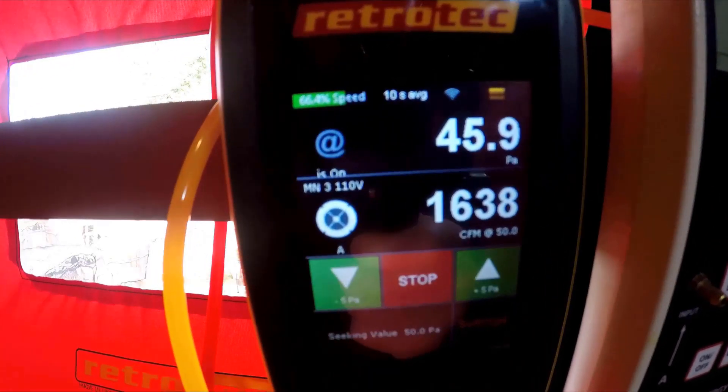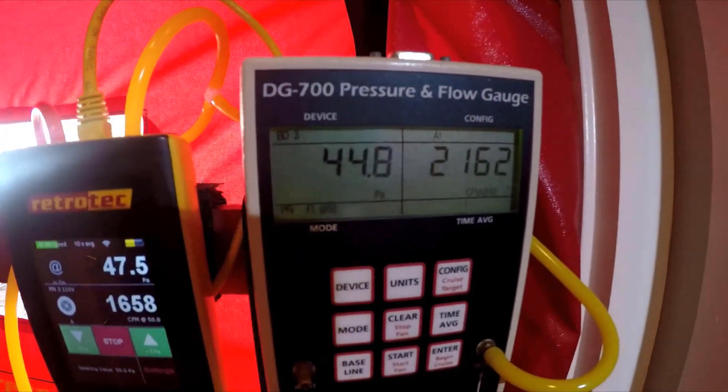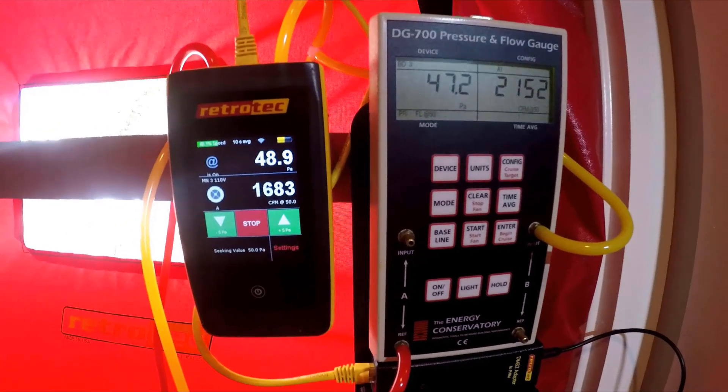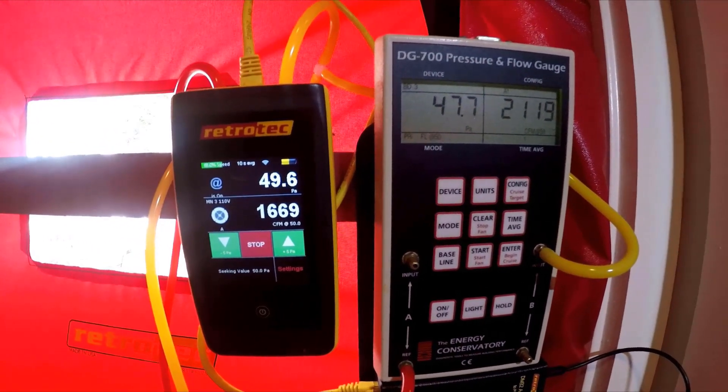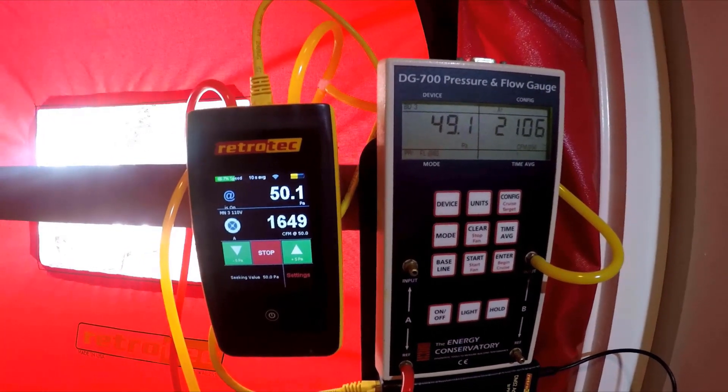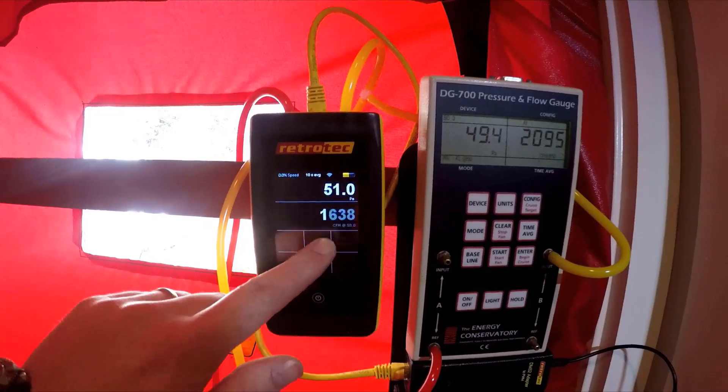And notice the difference that we have here in our readings. So we're almost to 50 or at about 1640 on the DM32 or over 2000 CFM on the DG700. So that's quite a big difference. Usually you'll have a reading that's 20% high in this scenario on the DG700 if that extra tubing is not connected.